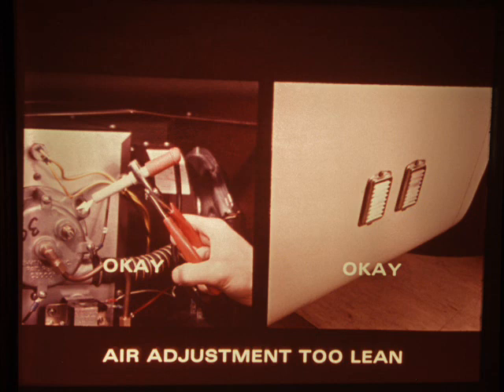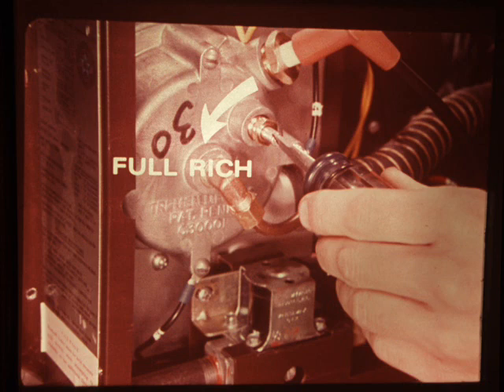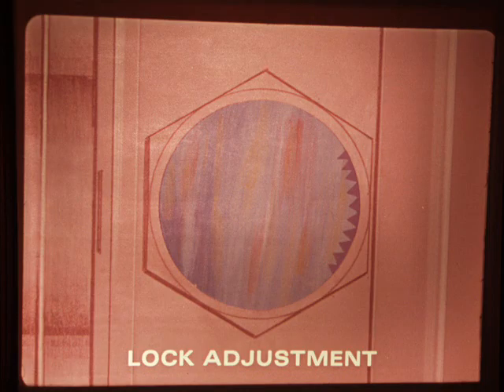Now, if you have a spark, and if gas flows through okay, the reason why the burner won't light is because the primary air adjustment is too lean. To fix it, loosen the hex lock nut slightly and turn the adjusting screw counterclockwise to the full rich position. Start the furnace by setting the thermostat to call for heat. Then watch the burner through the sight glass and turn the adjusting screw until you see a slightly yellow flame with green cones at the ports in the burner. Turn the screw a slight bit further so that the yellow disappears and the cones are sharp and blue. That is the correct adjustment, so hold the adjustment with the screwdriver while you tighten the hex nut.